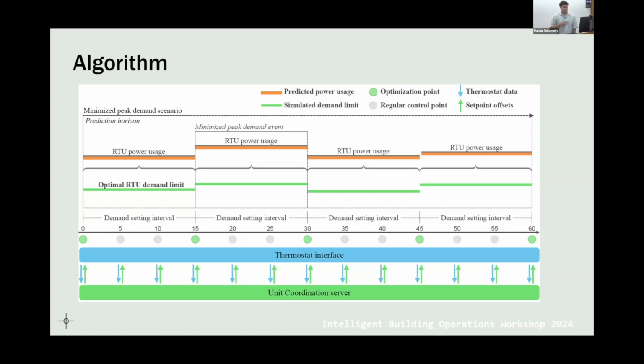And so in order to allow cooling loads into other zones, aside from the ones that were originally assigned at the initial 15-minute optimization, it will shuffle at the 5-minute marks. So we'll shuffle the units in order of priority in order to deliver cooling loads to the other zones in the building.